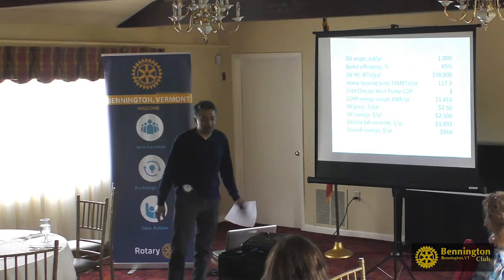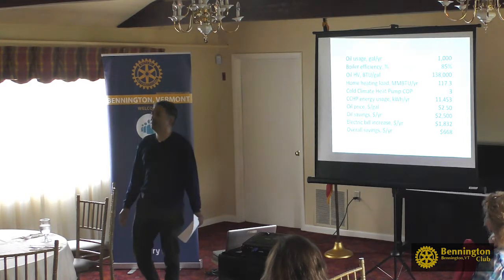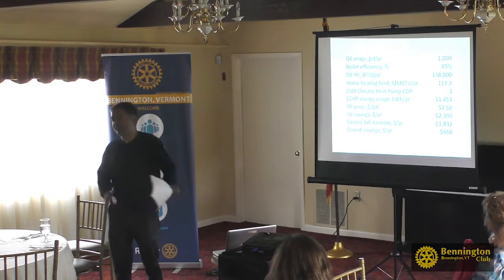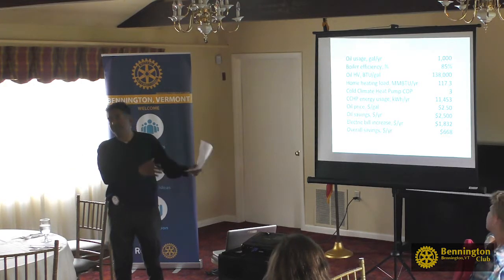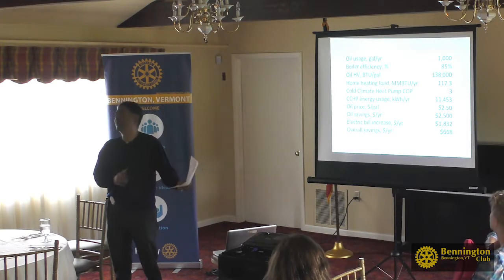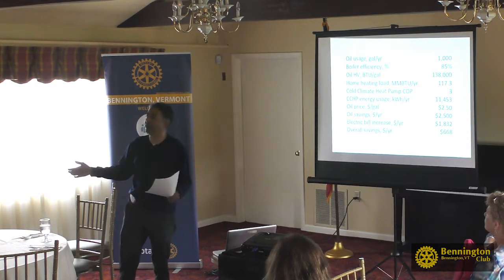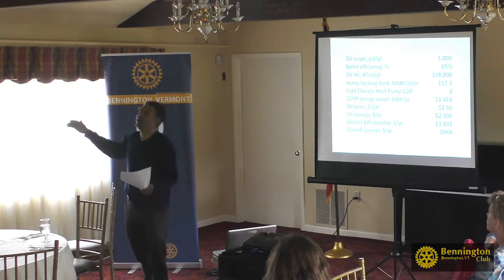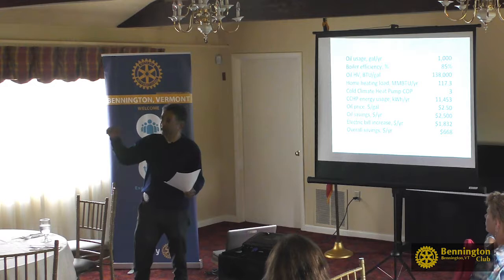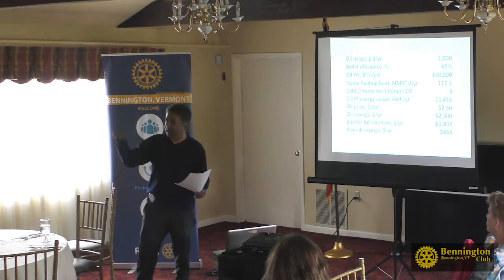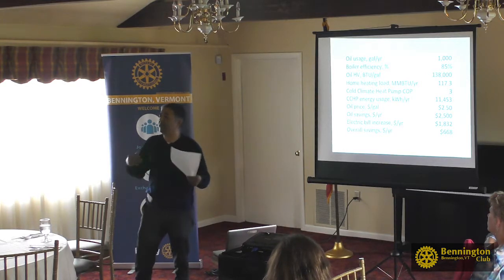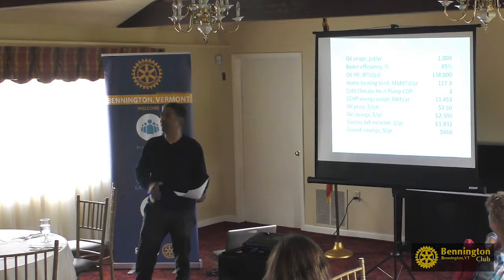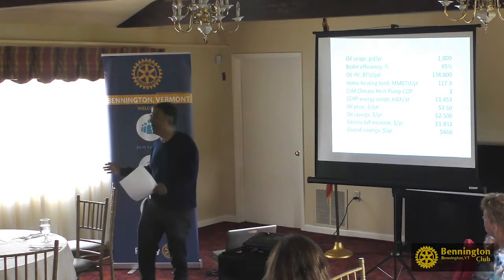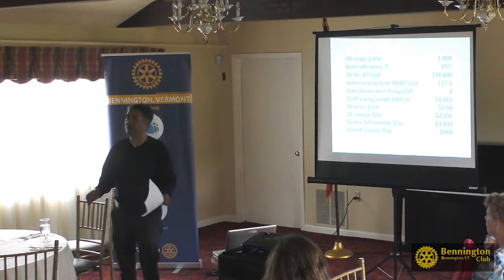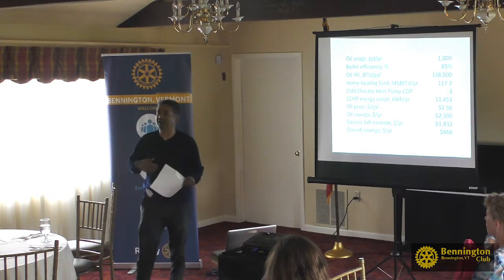So its energy usage is going to be about 11,000 kilowatt hours of electricity. This assumes that you can displace all the 1,000 gallons of oil, but in reality you cannot. You could probably displace about 75–80% of it. Why is that? Because as the temperature goes down, it loses its capacity as well. As the ambient temperature drops below about 5 degrees or so, its capacity also drops. At some point, the heat pump itself shuts off. So you have to have a backup system. You cannot just rely on a heat pump.